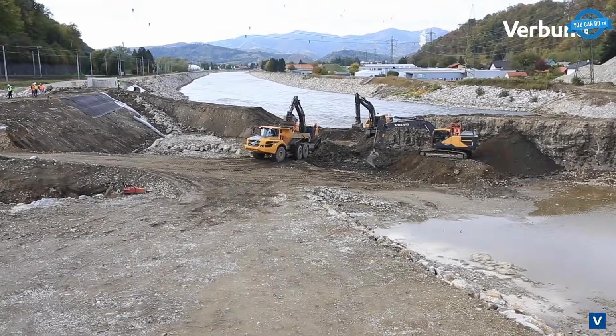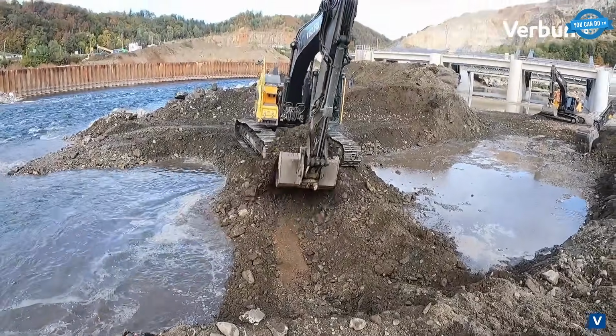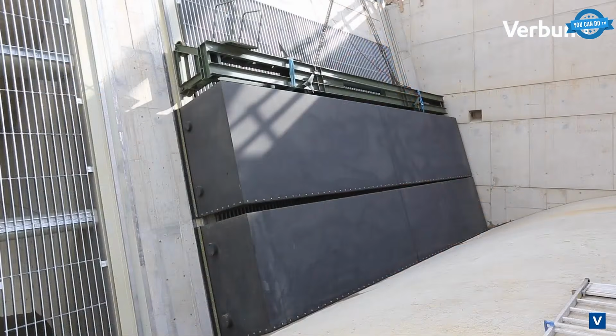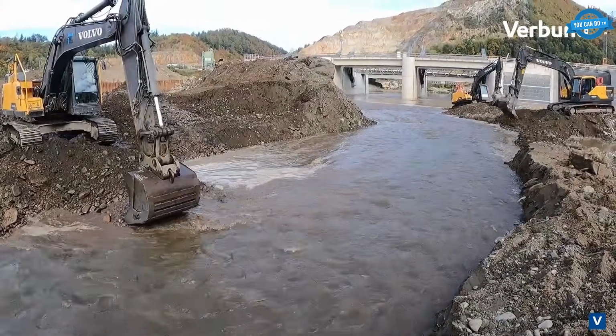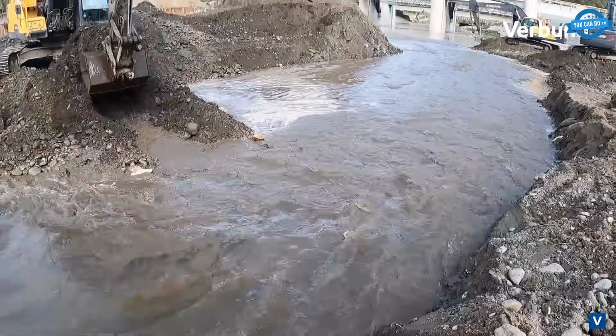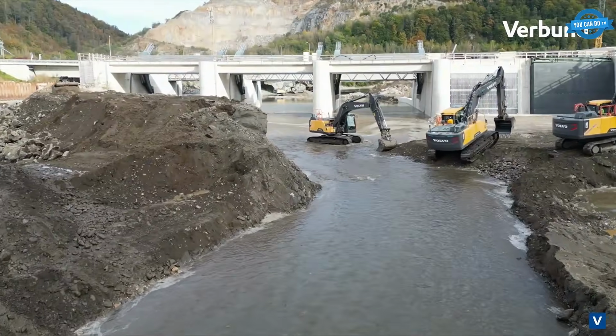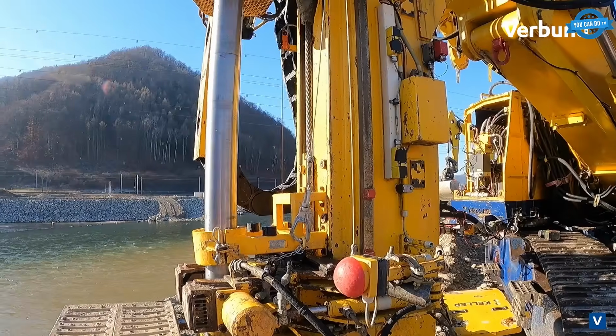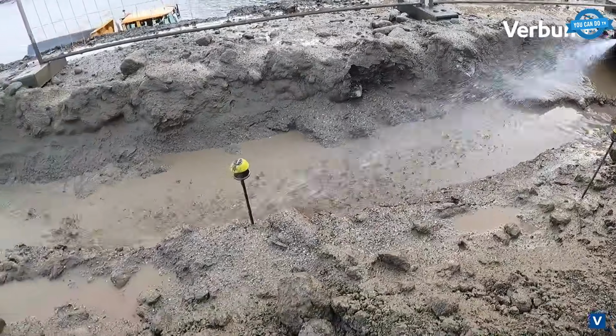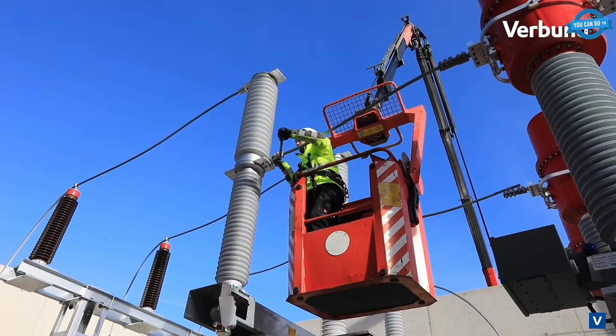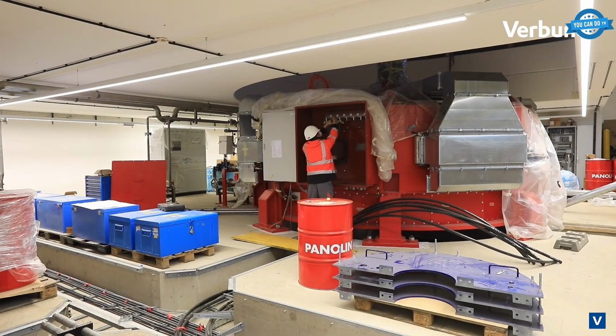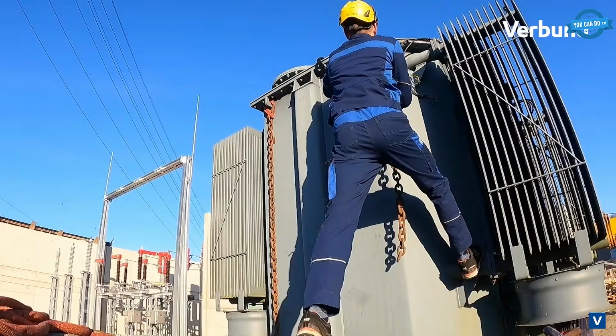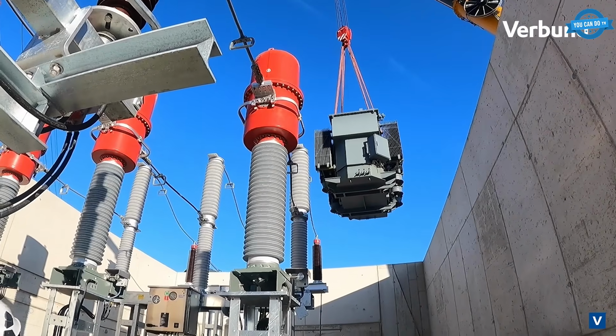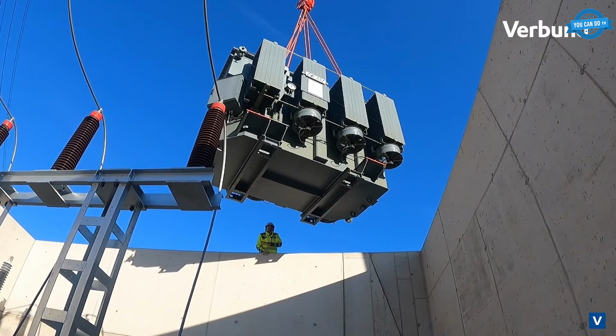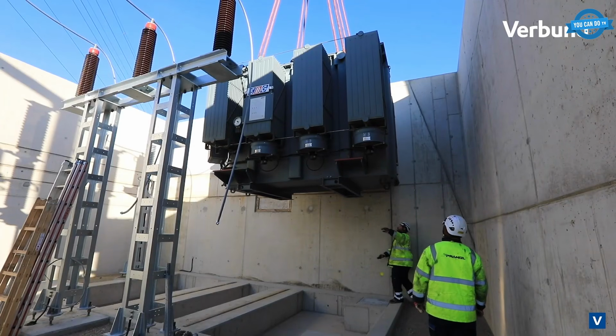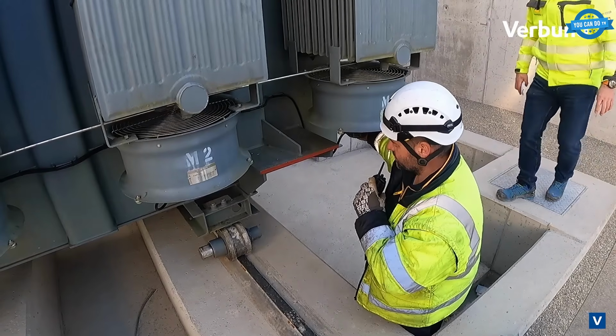After the turbines, the river itself gets moved. The temporary diversion dam goes down, and the Mur flows through the new weir for the first time. The transformer powering up the new Mur plant has run for 2 decades already, pulled from a sister hydropower station and rebuilt to current standards. A heavy mobile crane lifts the unit over the substation wall, lowers it onto rollers, and crews ease it along rails to its final position.